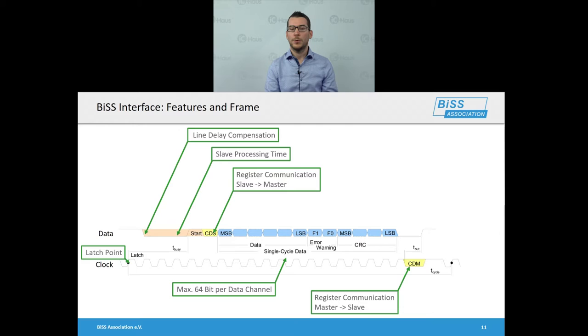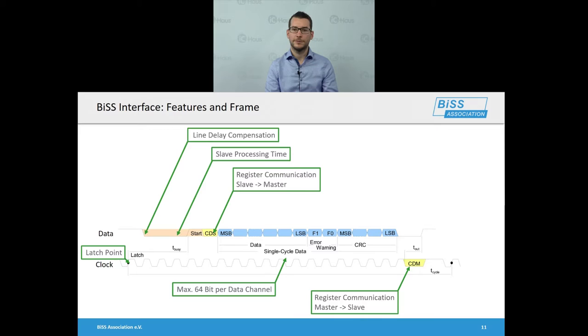This is why we call it a bi-directional interface — the control data communication. One bit of control data is transmitted from master to slave and one bit from slave to master in each frame. There is also a control data frame which spans several typical process data frames. You can use this control data, for example, to perform register communication such as calibration of a sensor, configuration of a sensor, reading out the electronic data sheet of a sensor, or retrieving temperature data stored in the slave's memory.